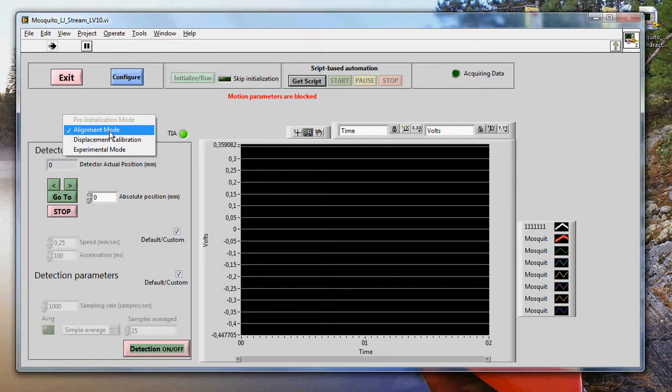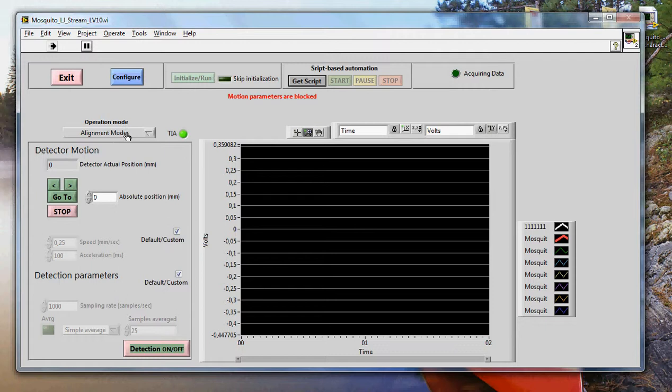This is where you choose the operation mode. We're now in alignment mode, which is like a scope mode. It is a mode of acquisition that helps you see if everything is okay with the mosquito, if the laser is on, if the transducer is okay, if the sample is okay. So this is a mode of acquisition which is slower than other modes and allows you to set up your experiment to do some debugging and so on.